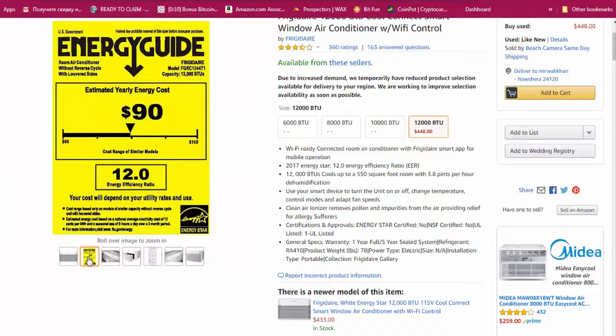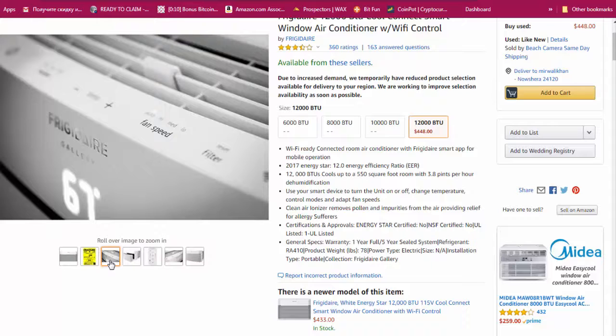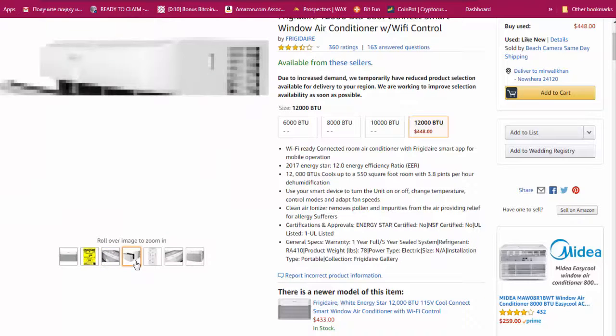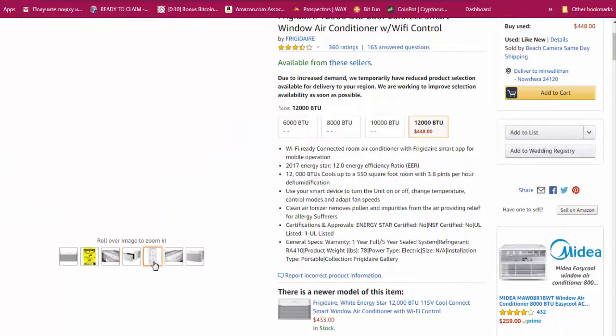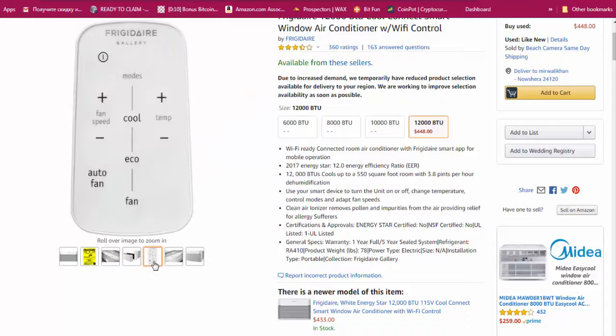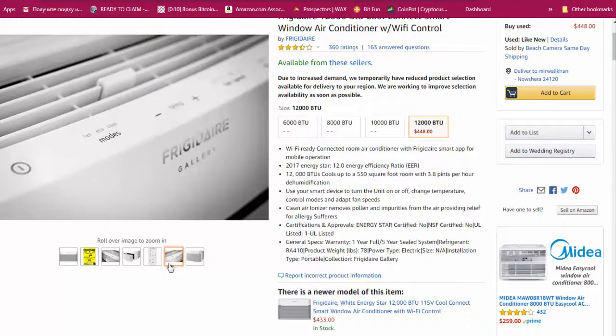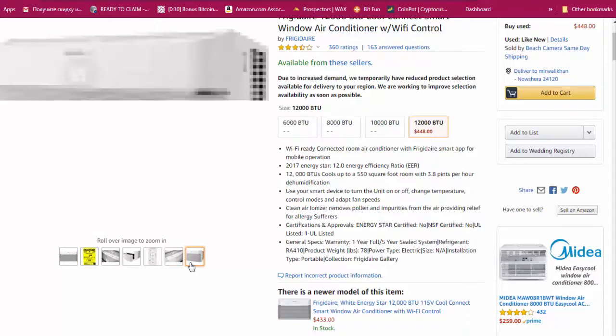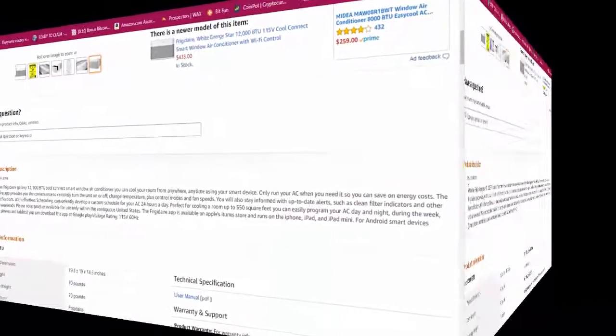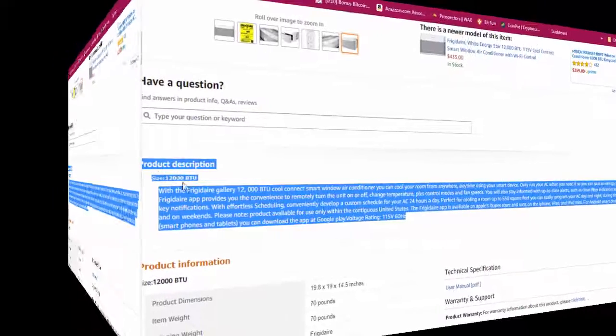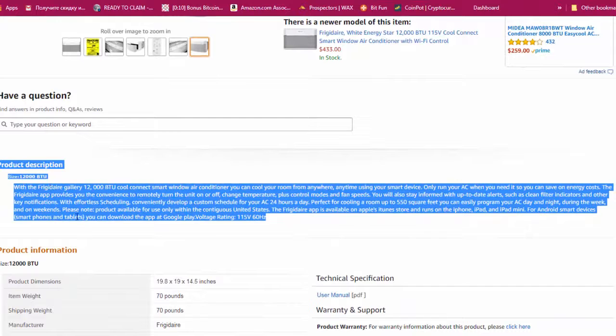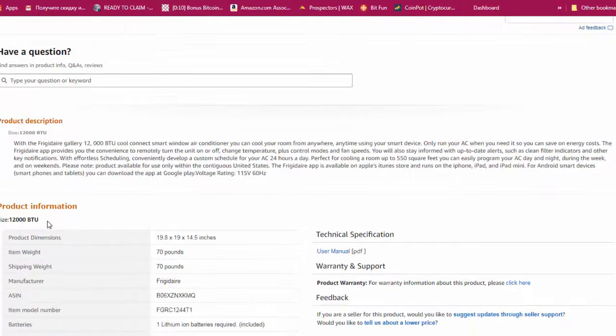Here's how to pick the right type for your space. Window units are sized according to their cooling capacities, measured in British thermal units, or BTUs, and they typically range in cooling power from 5,000 to 12,500 BTUs, but you can find higher BTUs. Generally, 5,000 to 6,000 BTUs will cool a 100 to 300 square foot room. 7,000 to 8,500 BTUs can cool a 250 to 400 square foot space. And 9,800 to 12,500 BTUs should cover anything from 350 to about 650 square feet.